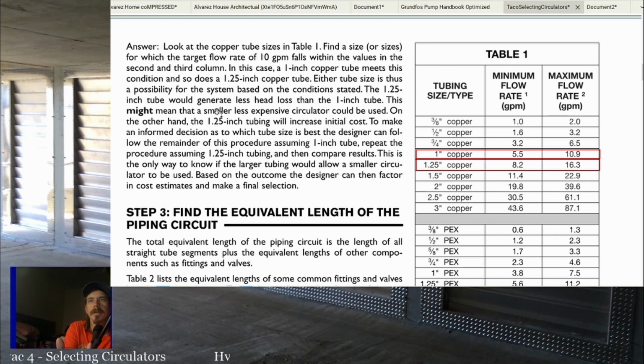On the other hand, 1.25-inch tubing is more expensive to install, right? If you need to run 200 feet of this pipe, then there's a difference between 1 inch and 1.25 inches. And I know it seems like a small point, especially if you do service a lot. Is it really that big of a difference? Well, it can be. So generally, you always want to strike a balance with what you're doing. The 1.25-inch pipe is going to be more expensive up front.